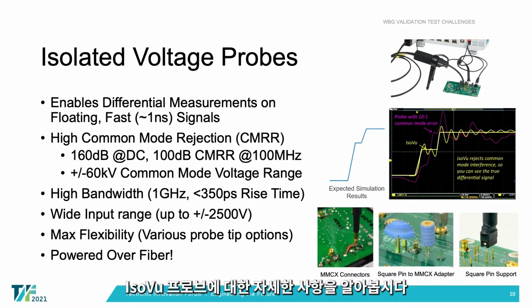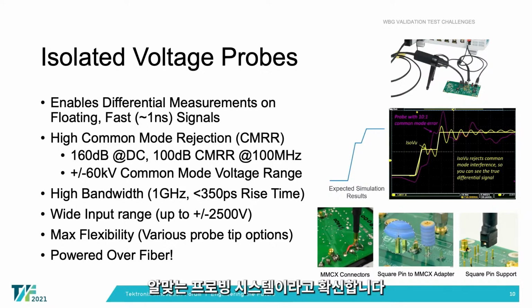Let's look at some more details about the IsoVu probes. IsoVu technology is the only differential probing system for wide-bandgap testing. Some of the important attributes of this probe, which make it suitable for wide-bandgap measurements, are high CMRR, high bandwidth up to 1 GHz with less than 350 picosecond rise time, support for up to 60 kV common mode, and a wide input range up to 2500 volts.